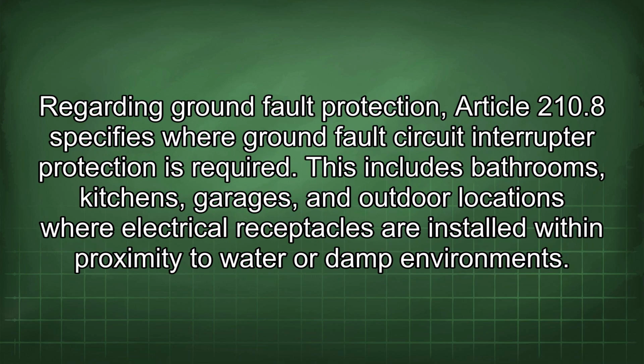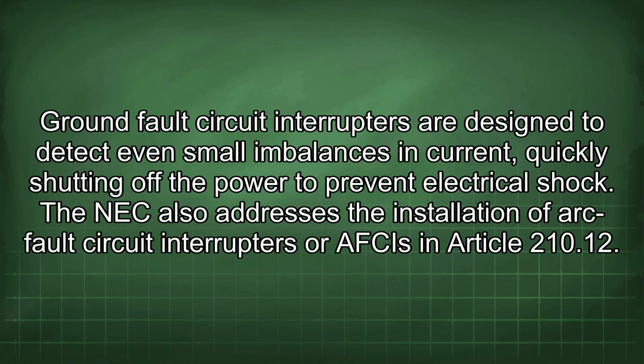Regarding ground fault protection, Section 210.8 specifies where ground fault circuit interrupter protection is required. This includes bathrooms, kitchens, garages, and outdoor locations where electrical receptacles are installed within proximity to water or damp environments. Ground fault circuit interrupters are designed to detect even small imbalances in current, quickly shutting off the power to prevent electrical shock.